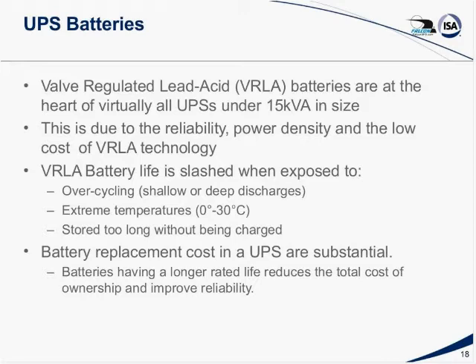Another issue is battery replacement cost, which is a substantial part of the UPS cost. So you want to look for batteries. Not all batteries are alike. You want to look for the rated service life of the battery. A battery with a longer rated service life is going to give you a lower cost of ownership of the UPS.